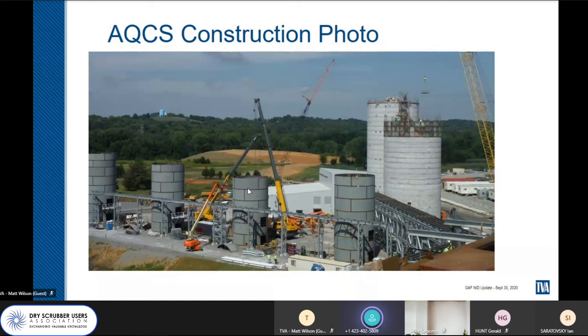Operations operates to, we've seen it 2 different ways, but around 200 or 210 degrees Fahrenheit for 100% PRB fuel, and for 15% Illinois Basin fuel, we operate to about 190 degrees Fahrenheit. So the answer is the outlet temperature. It's the way that we do that, and constant monitoring of the dropout into that J-duct reactor into the grid screw.